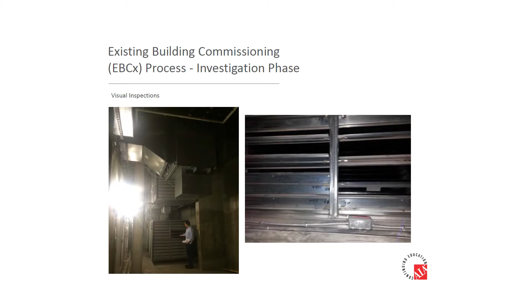We were able to pick up some things very early on without really even needing to look at the controls yet. For example, on the left there, that's my colleague working with a backdraft damper on the return fans in the system - you can see he's got them held open, that's what they're supposed to look like when the fan is running. Unfortunately, that's not what they looked like when the fans were running - they were all kind of pointed down towards the floor, what I like to call droopy backdraft dampers. That was ultimately really affecting the flow in the system, and was something that explained a lot about some of the issues these guys were having. We'll circle back to that later on.